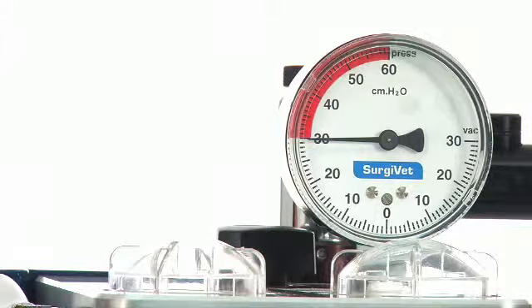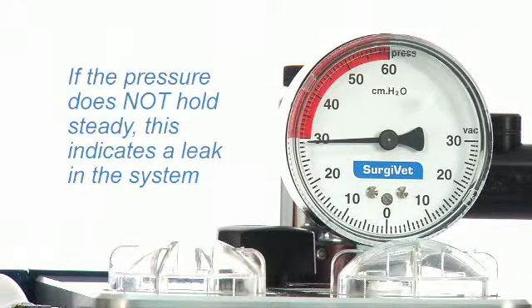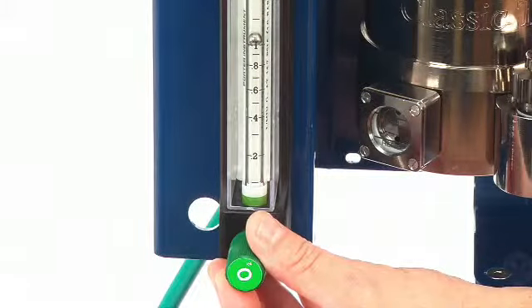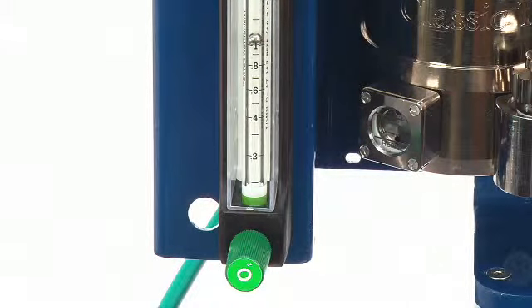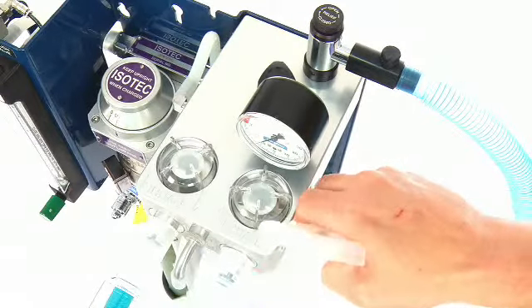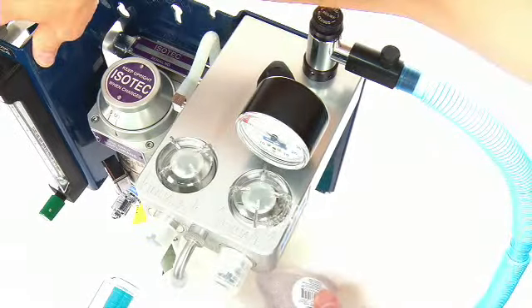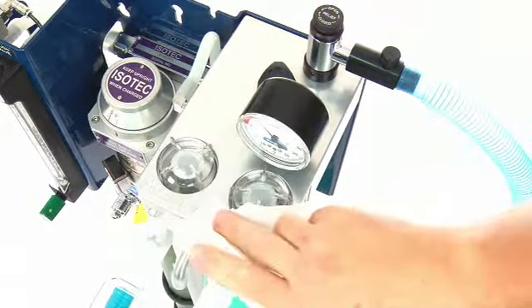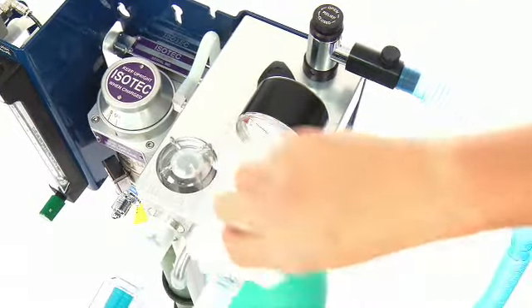The pressure should not drop more than 5 centimeters of water in 10 seconds. Ensure that the pressure holds steady. If it does not hold steady pressure and continues to decrease, this indicates a leak in the system. Turn the dial on the O2 flow meter up to compensate for the leak, and use a soapy water solution to spray on the machine parts to locate the leak. Use a dry towel to wipe the areas after spraying.